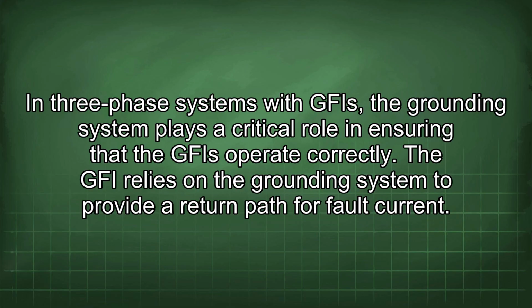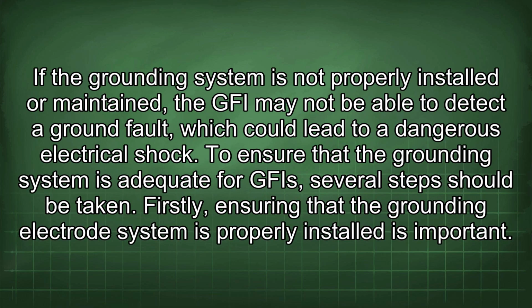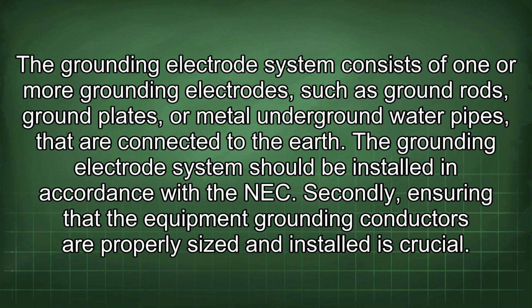The GFI relies on the grounding system to provide a return path for fault current. If the grounding system is not properly installed or maintained, the GFI may not be able to detect the ground fault, which could lead to a dangerous electrical shock. To ensure that the grounding system is adequate for GFI, several steps should be taken. Firstly, ensuring that the grounding electrode system is properly installed is important. The grounding electrode system consists of one or more grounding electrodes, such as ground rods, ground plates, or metal underground water pipes that are connected to the earth. The grounding electrode system should be installed in accordance with the NEC.